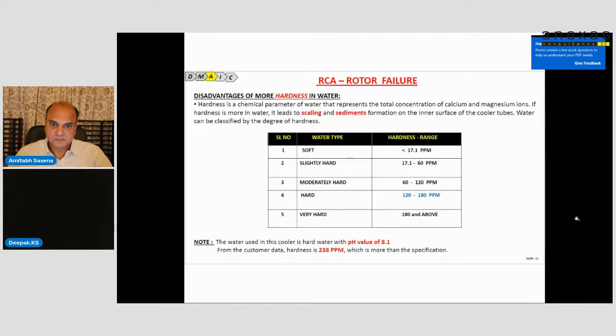what is the disadvantage of having more hardness in water? Yes, you can see the different water types: soft, slightly hard, moderately hard, hard, and very hard. The hard range of 120 to 180 ppm is our specification, but the water used in this cooler is hard water with a pH value of 8.1. The hardness is 238 ppm, which is more than the specification. It's not okay.